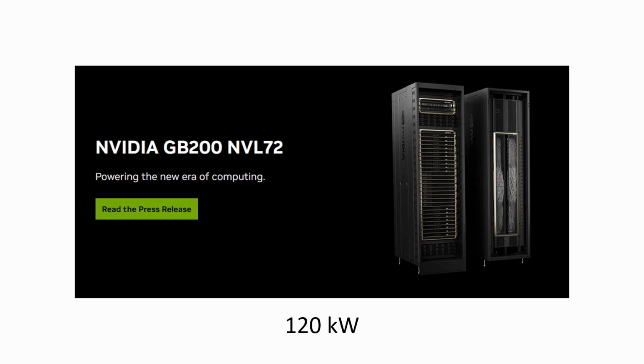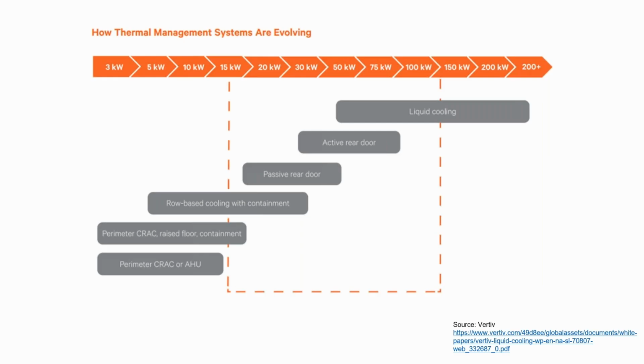If you've watched any one of our presentations before, you know this is what pushed us towards liquid cooling. Our source here is Vertiv on this one. This is a chart that they produced that shows off roughly the types of kW density you can cool with different technologies. So if we start way at the left in the 2010 era, where we were between 2.5 and 10 kW, well, then that perimeter CRAC or AHU type cooling worked, the raised floor containment. And then as we grow in heat density, we can still do air. Row-based cooling containment gets us into the 20 and 30 kW range according to Vertiv's data here.